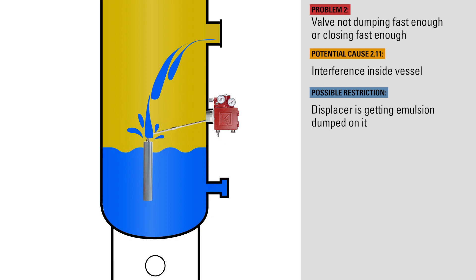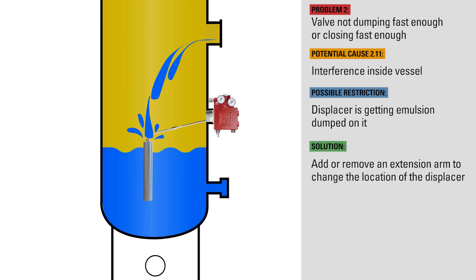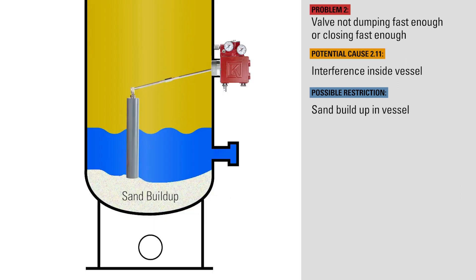If the displacer is located where it's getting emulsion dumped on it, this could cause erratic actuations from the controller. To remedy this, if there's room in the vessel, add or remove an extension arm to change the location of the displacer. If there's a lot of sand in your system, it can build up inside the vessel over time to the point where it restricts the downward movement of the displacer. In this case, you'll need to shut in the vessel and remove the sand.